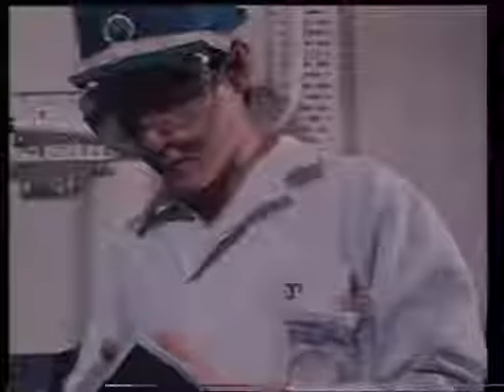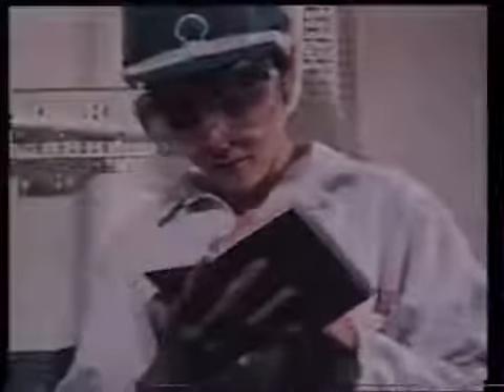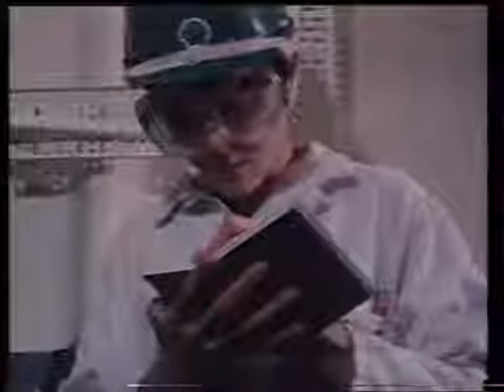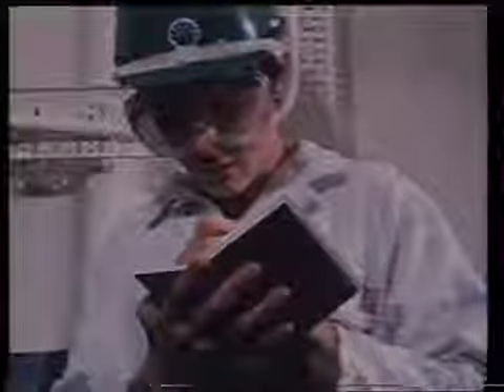Take care not to drop a metal object onto the battery top, as it may short out several cells, causing damage to the batteries, to the metal object, and this is most important, it could cause a fire. Full protective clothing must be worn for your safety. The terminals must be clean and tight and lightly greased with petroleum jelly. When you check the output voltage of your batteries, do not forget to disconnect the charger before you take the reading. Otherwise, you will read the charger's output voltage. A record should be kept of the date of service and any readings taken.